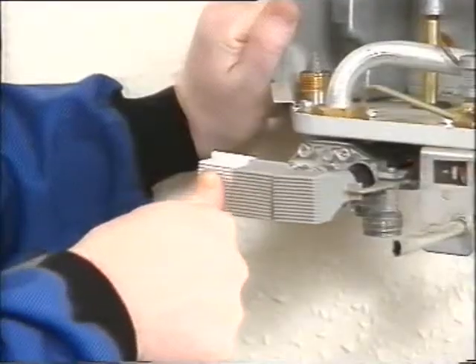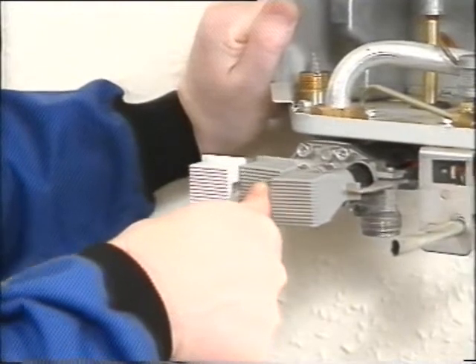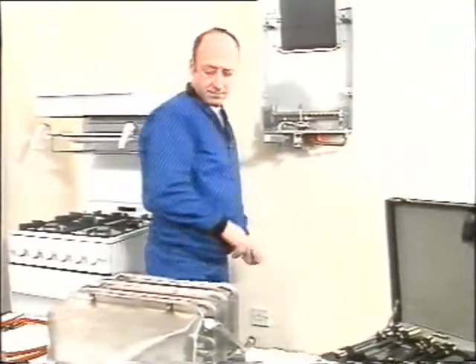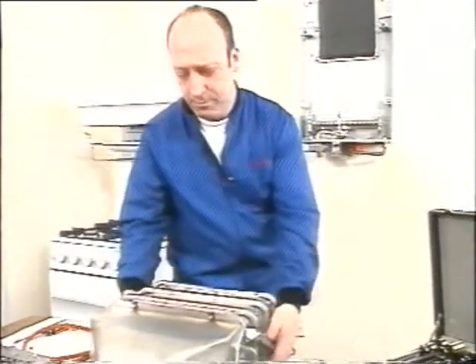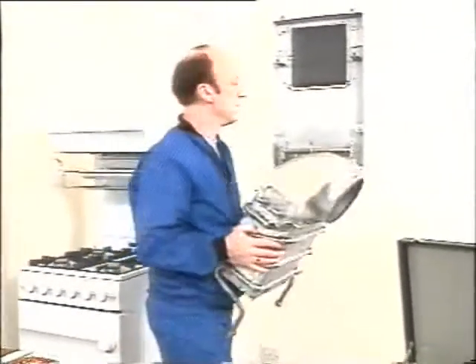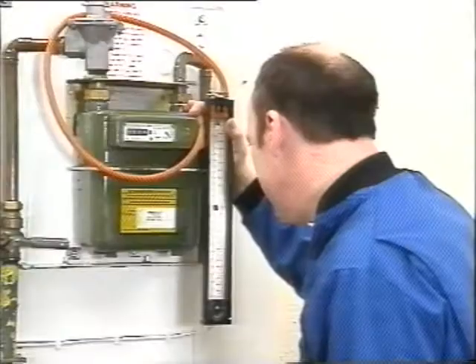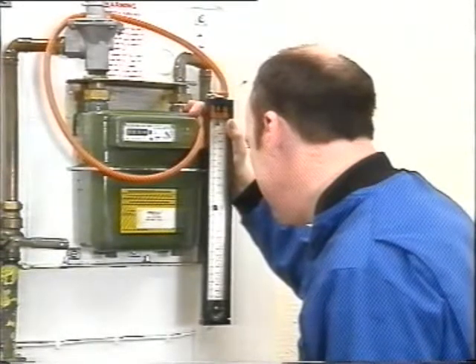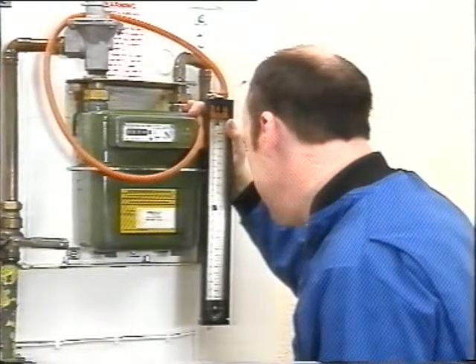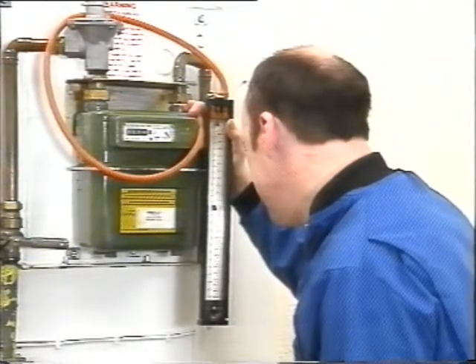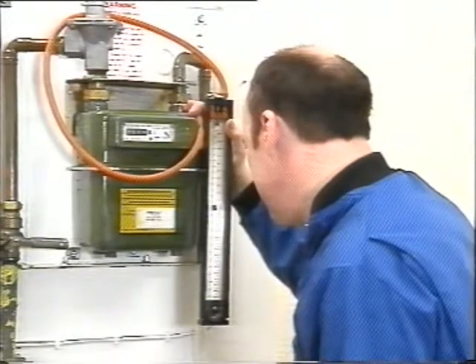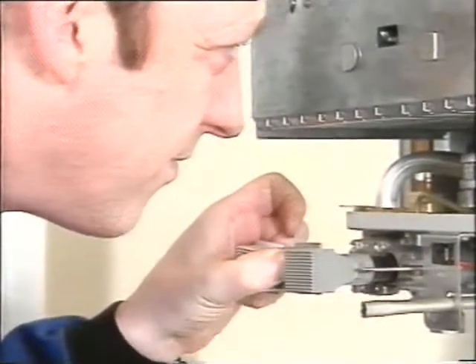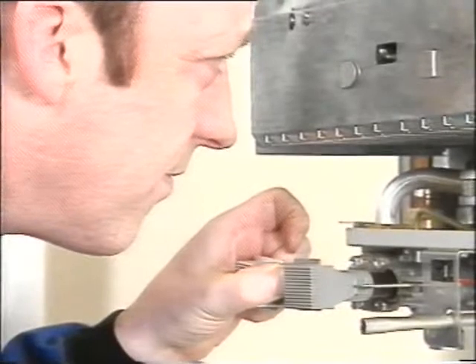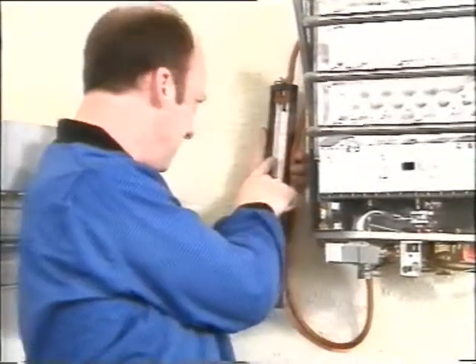If there are gas and water filters fitted, check them, and if necessary, grease the control valve push rods. When you're sure everything's clean and working properly, reassemble it all, renewing all the jointing washers as you do. Test the gas installation for soundness and make sure that there are no water leaks at the heat exchanger connections. Next, test the ignition device and the flame safety device. Then check the burner pressure.